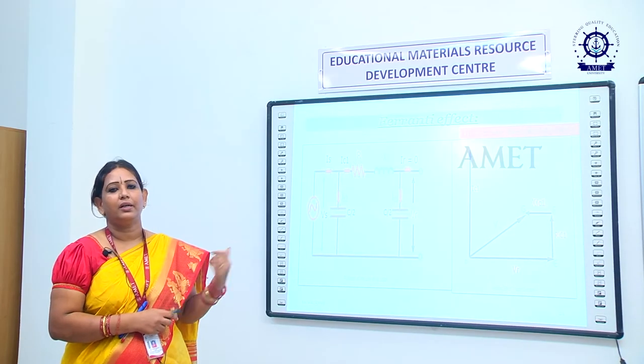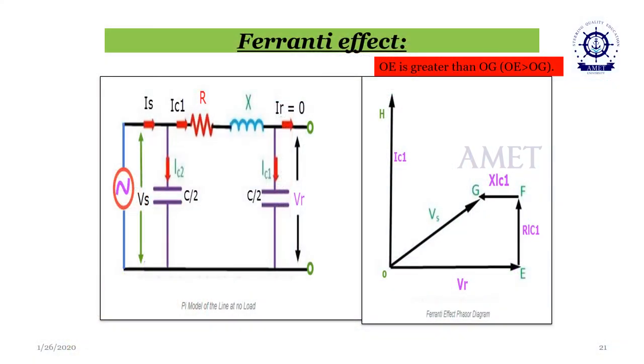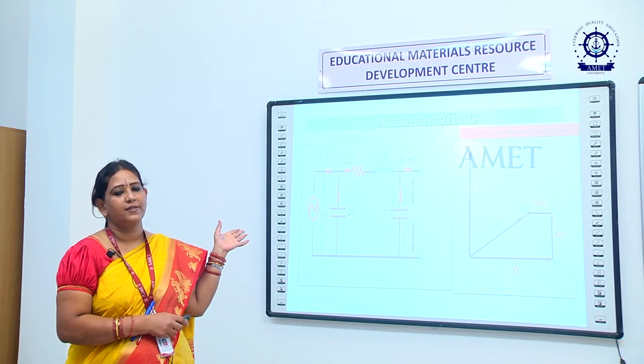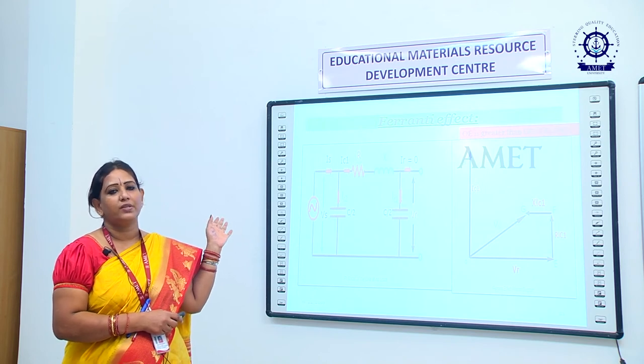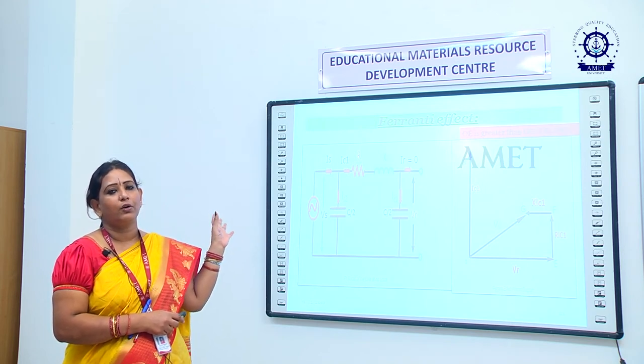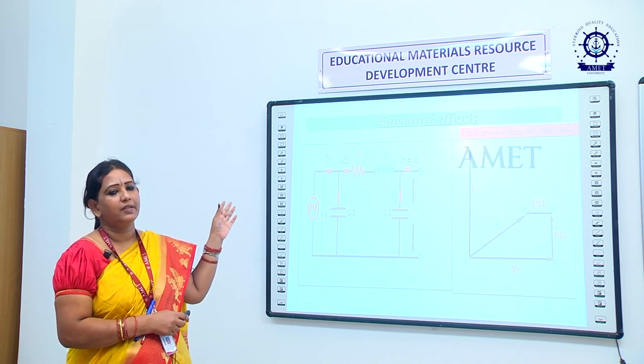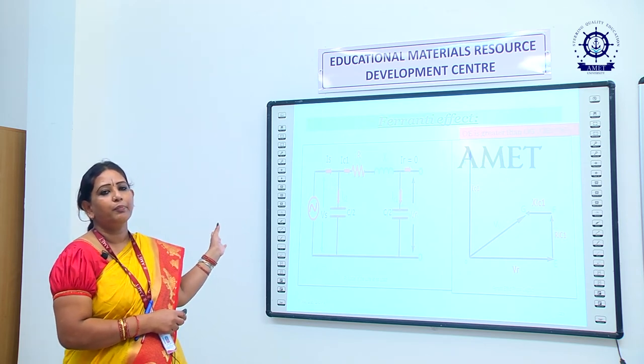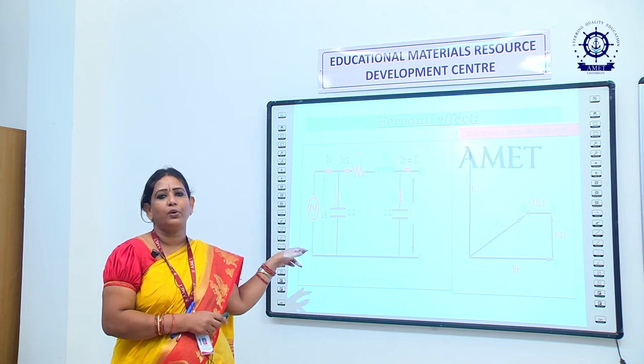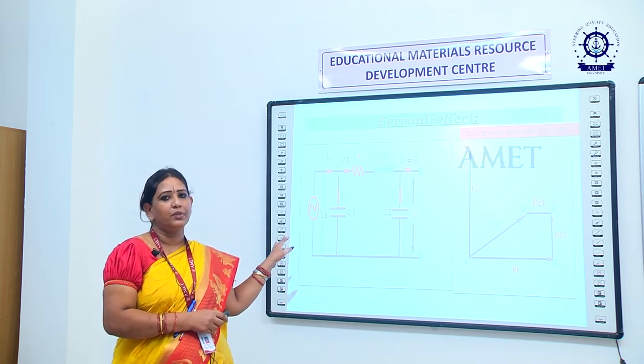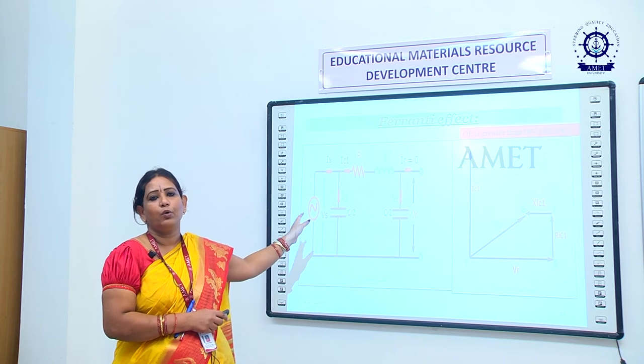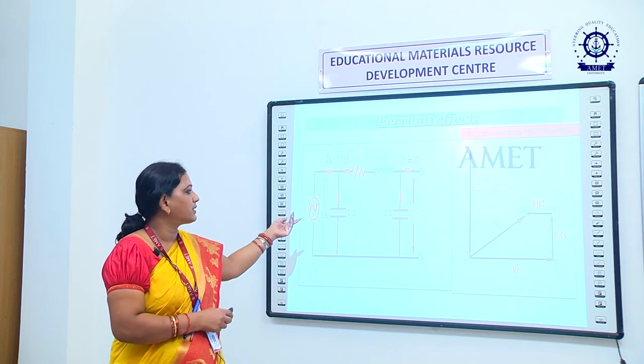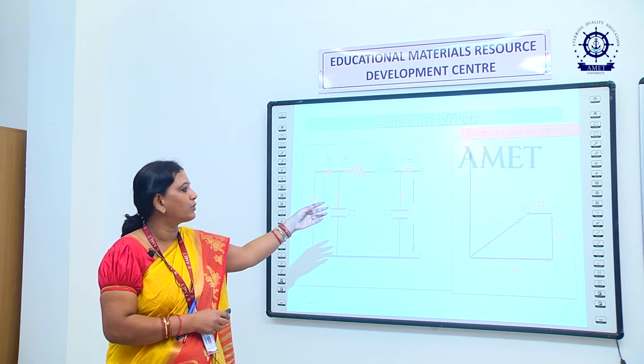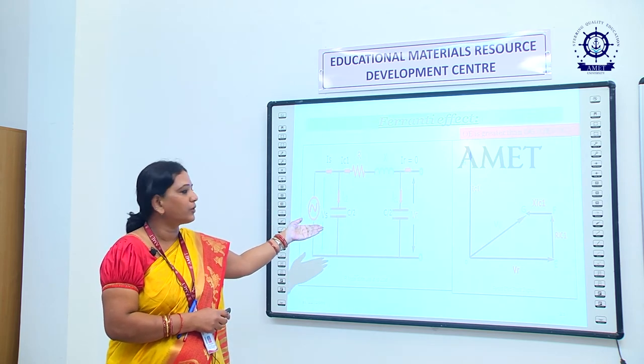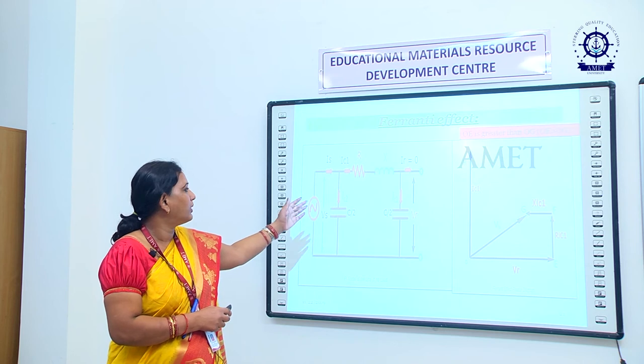So this is the mathematical explanation for the Ferranti effect. I have a transmission system, say a long transmission line, which has R, L and C. This is called a pi model, where the series element and shunt element are connected. The input voltage is Vs and the output voltage is Vr, the receiving end voltage. You can observe that since the output side is going to be lightly loaded or open circuited, the voltage VR is going to be greater than VS.